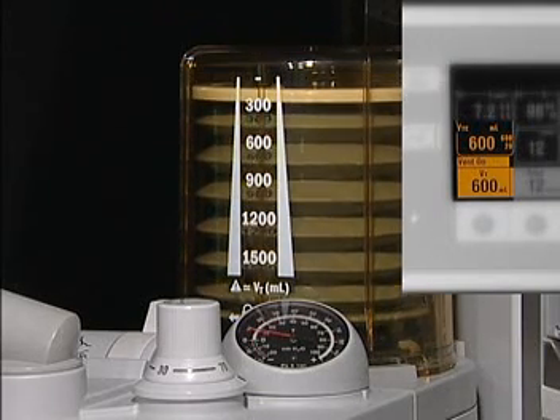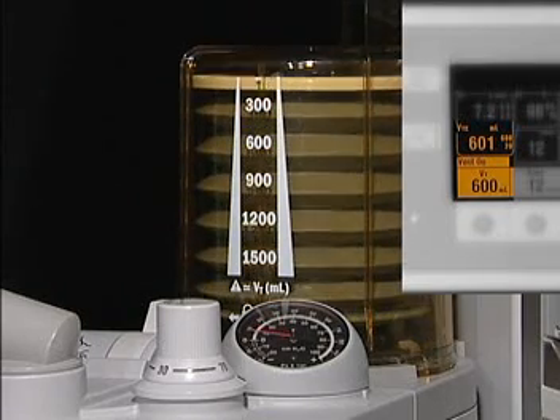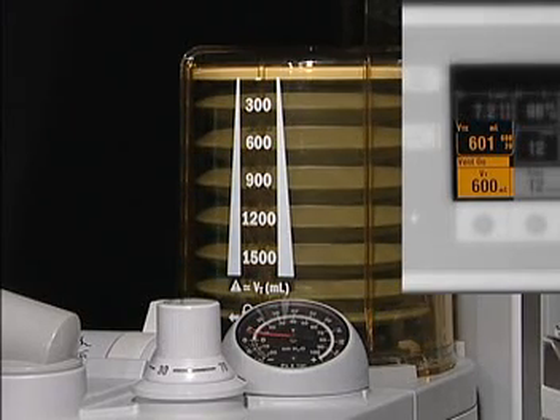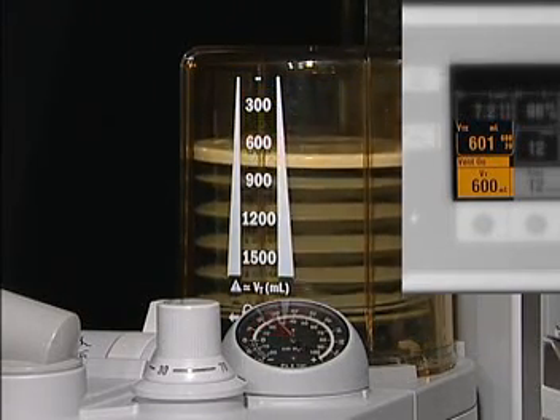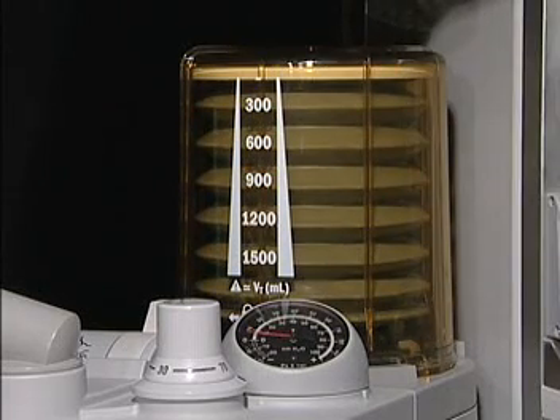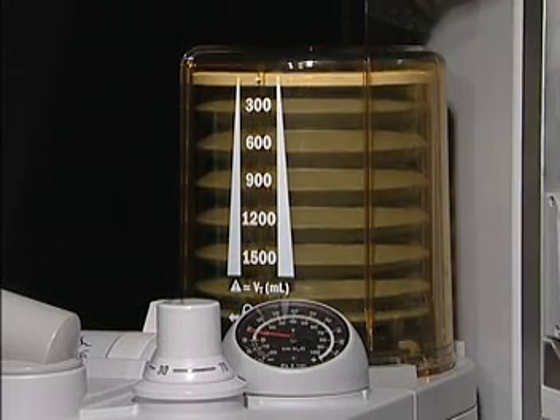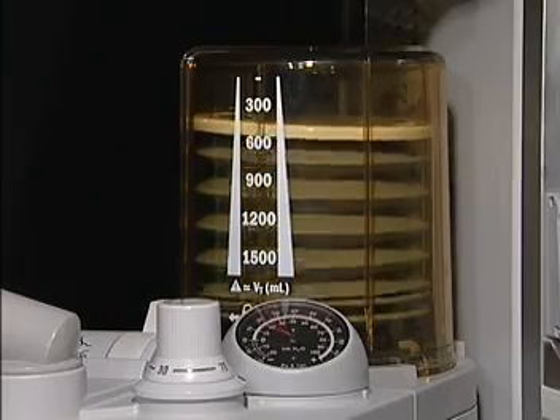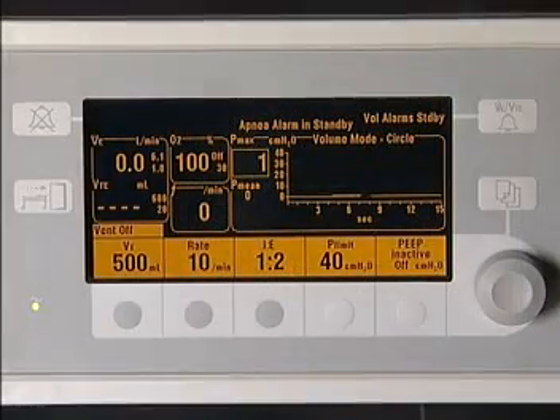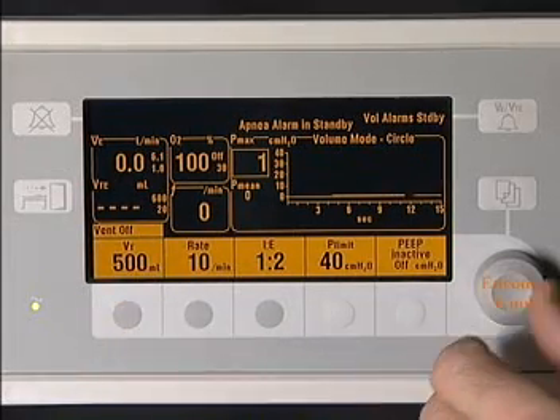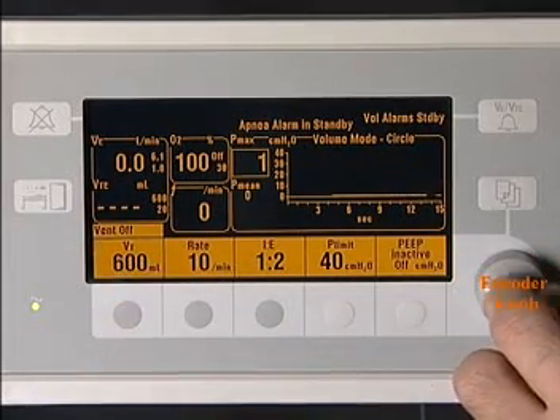The bellows housing provides a nominal indication of the volume delivered by the bellows. The actual travel of the bellows will not match the delivered tidal volume, since travel is increased to overcome compression and compliance losses and decreased to offset the contribution of fresh gas flow to the delivered breath. We refer to this feature as tidal volume compensation.